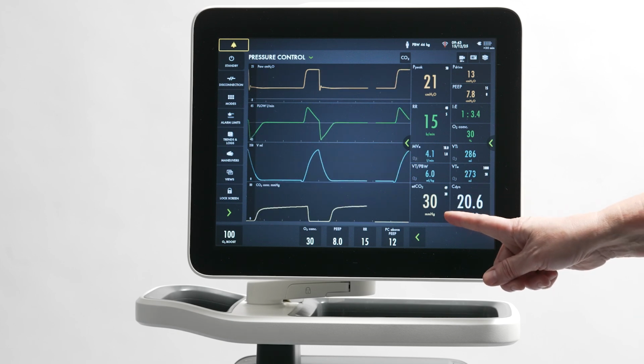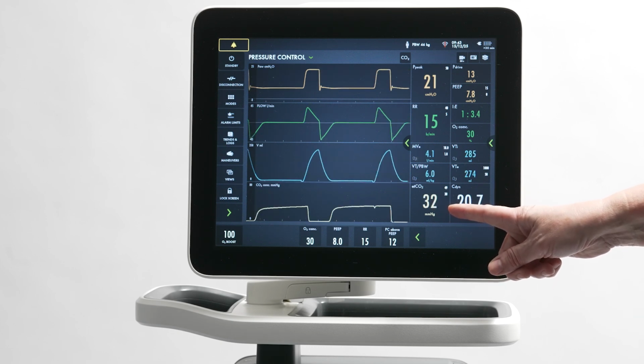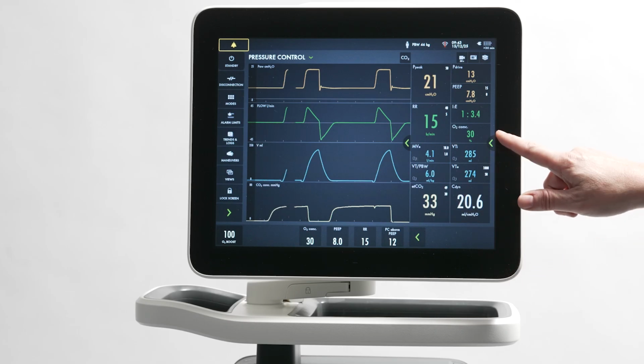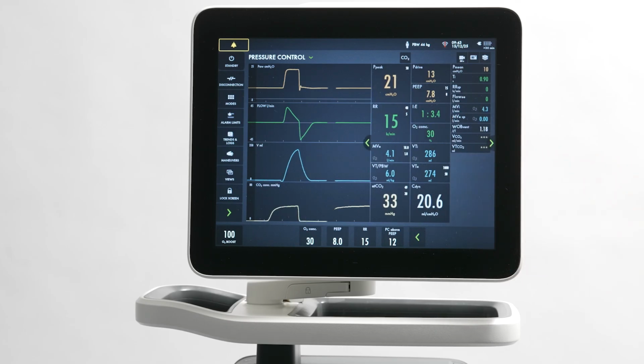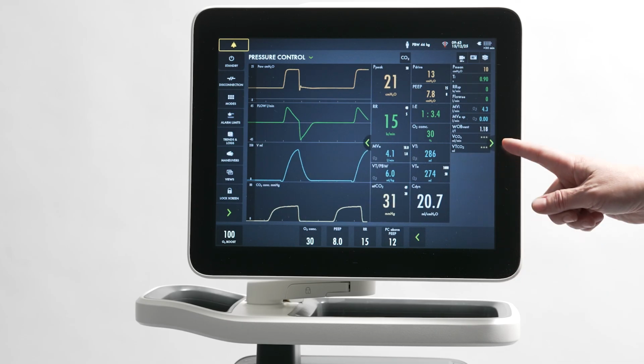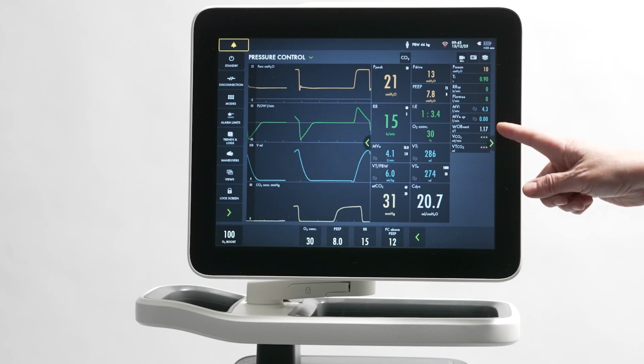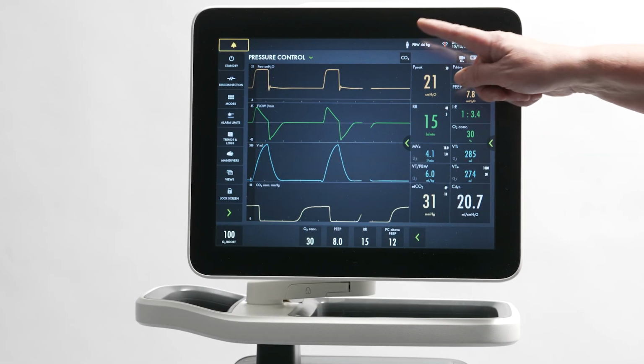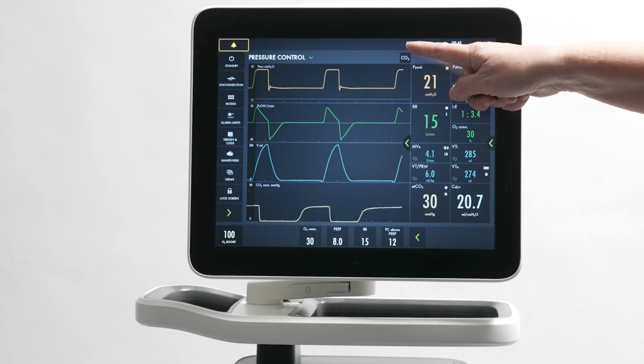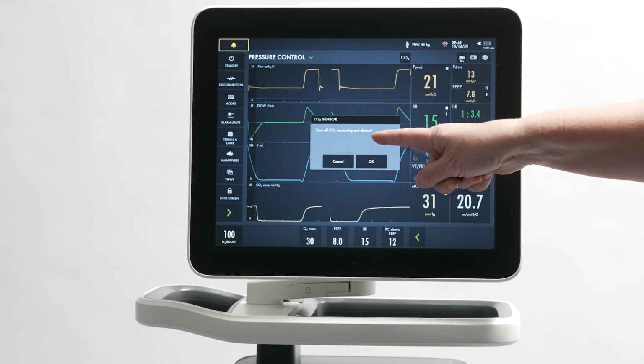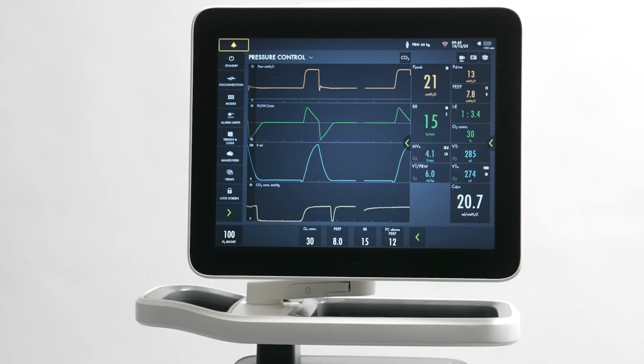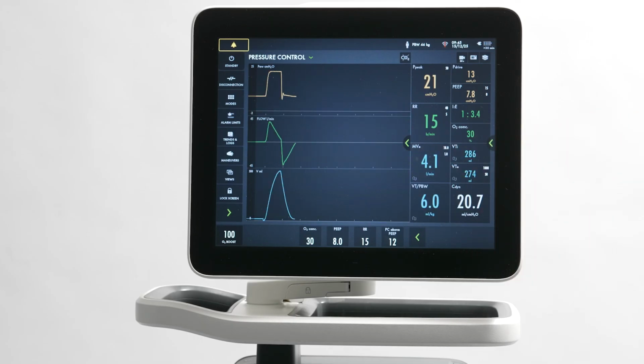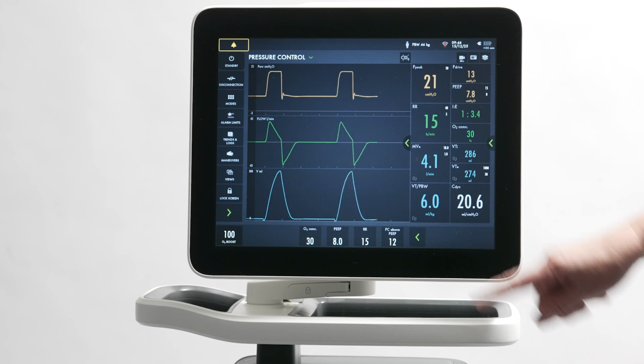You can find the etCO₂ here. By tapping the green arrow, you access the CO₂ minute elimination and the CO₂ tidal elimination. Once the CO₂ sensor is calibrated, you can enable or disable CO₂ monitoring and alarms by tapping the CO₂ button. Even if CO₂ monitoring is disabled, the sensor will retain the calibration.